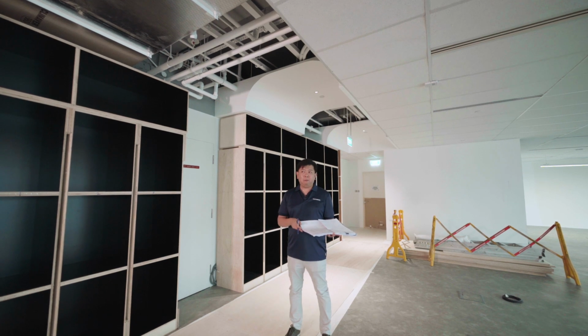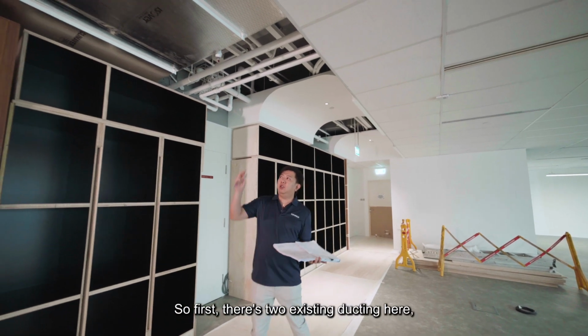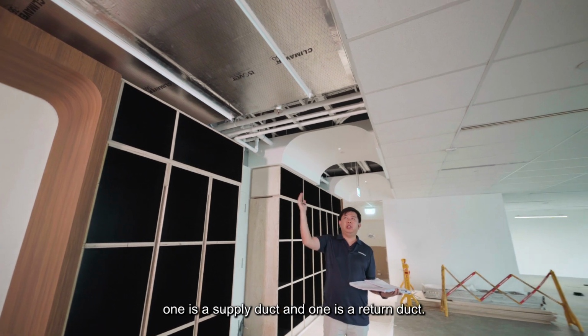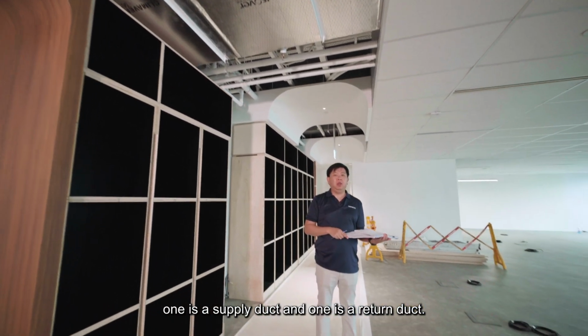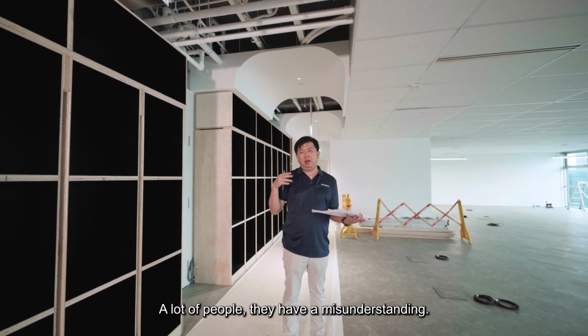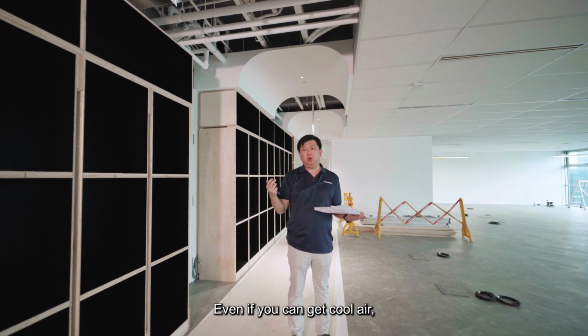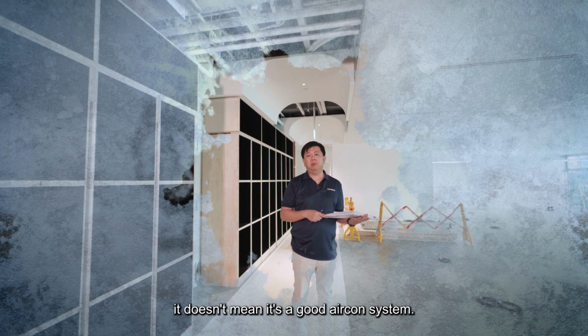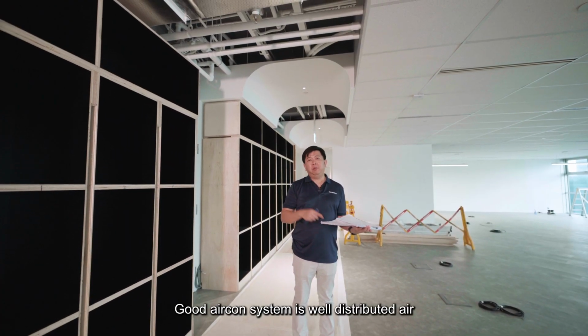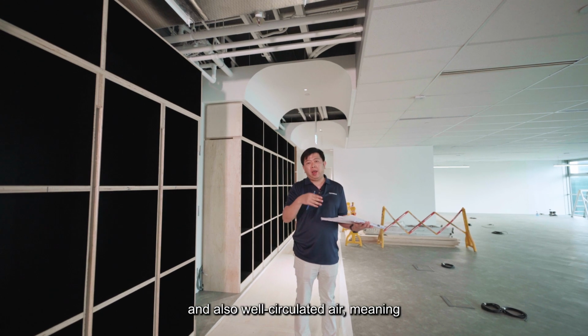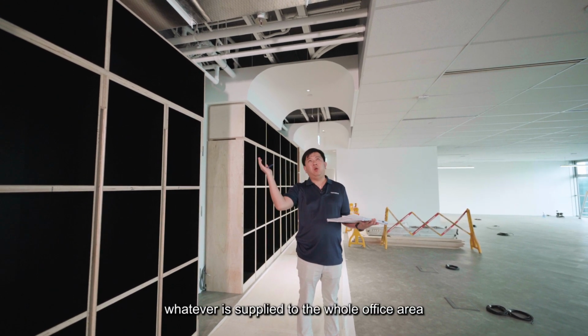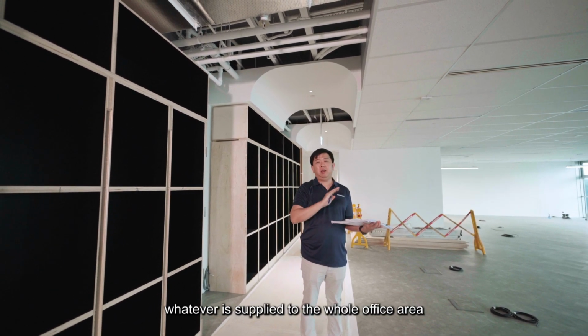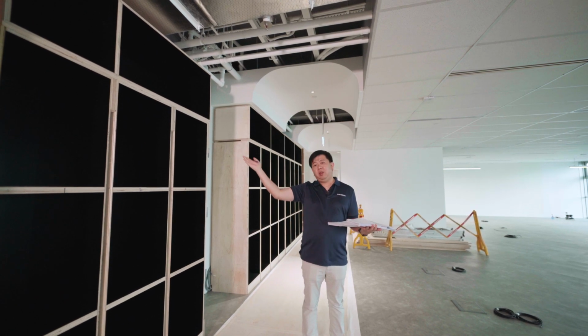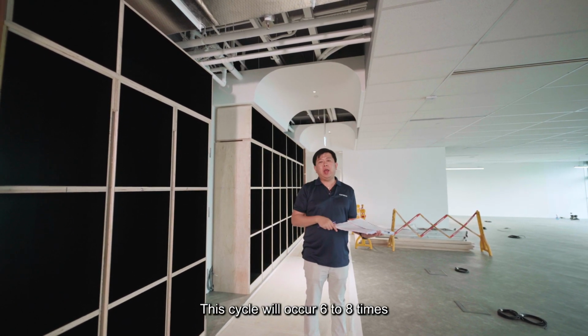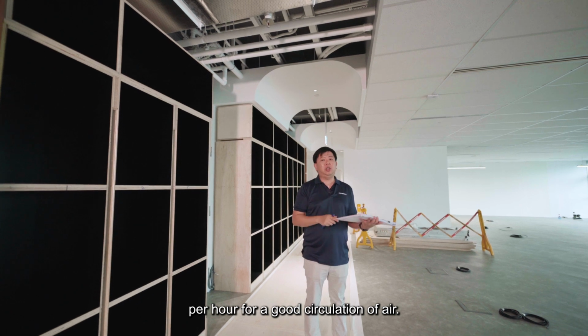So first, there are two existing ducts here: one is a supply duct and one is a return duct. A lot of people misunderstand — getting cool air doesn't mean it's a good aircon system. A good aircon system has well-distributed and well-circulated air, meaning whatever is supplied to the whole office area needs to be returned to the AHU, about 6 to 8 times per hour. That's good air circulation.